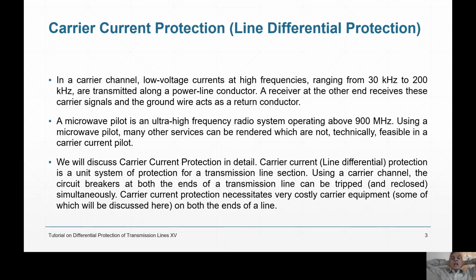See, carrier current protection or line differential protection is a unit system. Unit system means on both sides there are CTs, and between the two CTs is a zone of protection. If a fault occurs beyond the two CTs, the system should not operate. Using this carrier channel, the circuit breakers at both ends of a transmission line will trip simultaneously and reclose simultaneously. But the problem is that this carrier current protection necessitates very costly carrier equipment.